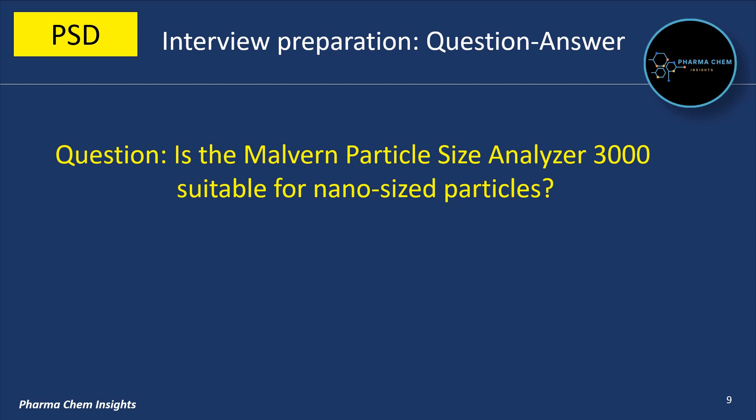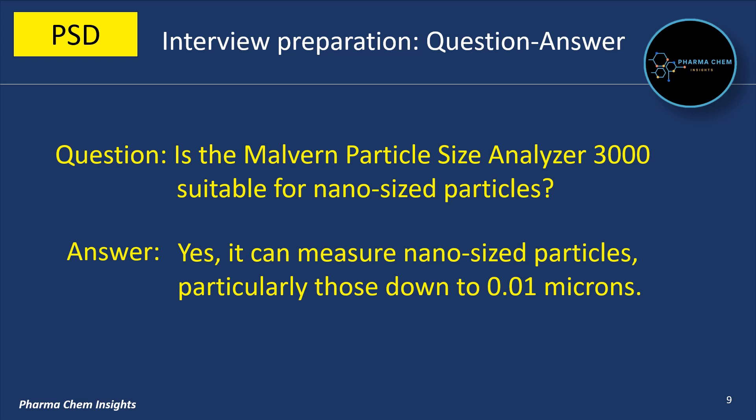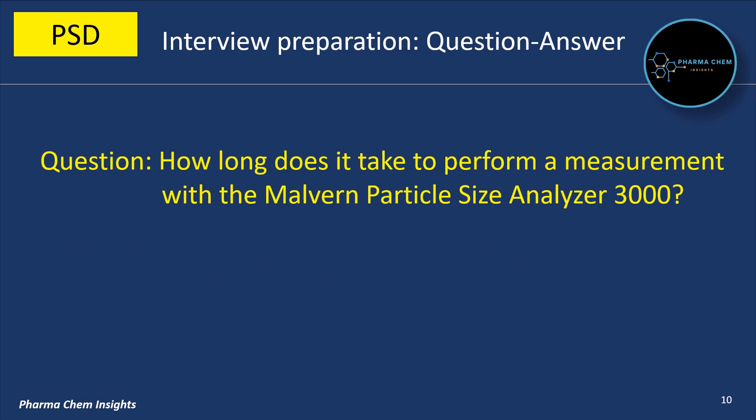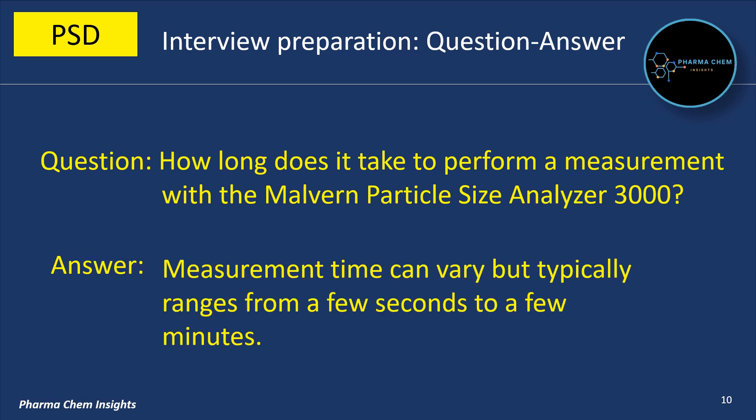Next question: is the Malvern Particle Size Analyzer 3000 suitable for nano-sized particles? Yes, it can measure nano-sized particles, particularly those down to 0.01 microns. How long does it take to perform a measurement? Measurement time can vary but typically ranges from a few seconds to a few minutes.